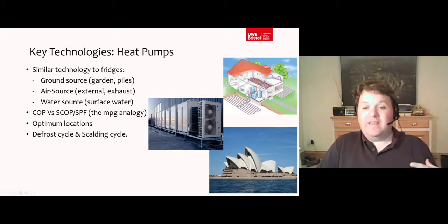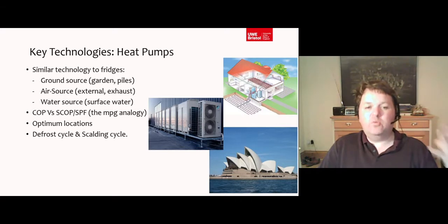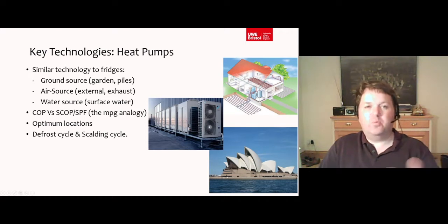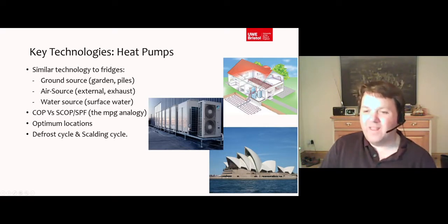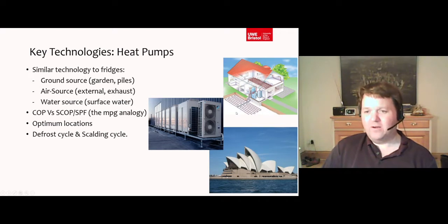Because you're pumping heat out of the air or out of the garden, the source can actually get down to freezing level. A lot of these kits are tested in places like Germany where they have much drier winters; we have very humid winters and so the risk of freezing over is higher here. If you freeze over, you have to reverse the system and defrost it, which uses up more energy and your seasonal COP will be worse as a result. This is one reason why ground source heat pumps are actually more efficient than air source — the temperature is more constant and less likely to freeze.